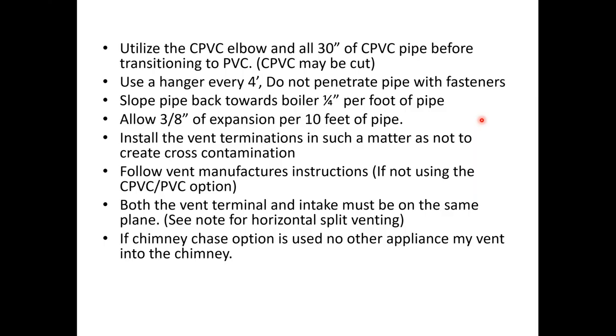So we have a vent kit we'll go over just a little bit that includes everything you need to then transition over to PVC. We want to try and put a hanger every 4 feet, and don't penetrate the pipe with fasteners. Don't zip screw your banding iron directly to your vent pipe. We want to slope that pipe back towards the boiler.